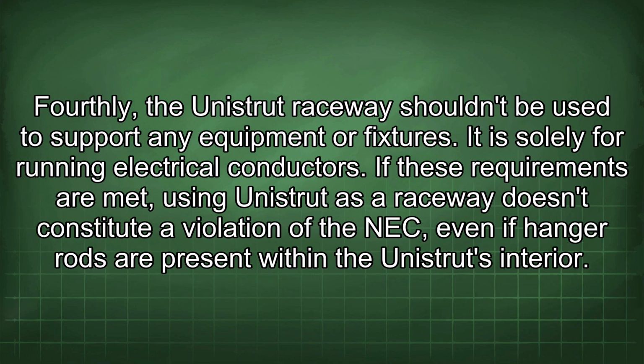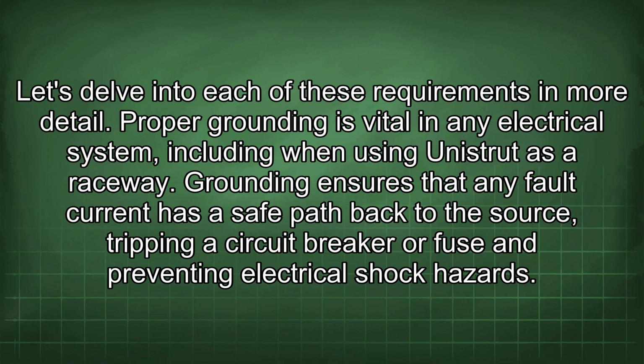Fourthly, the Unistrut raceway shouldn't be used to support any equipment or fixtures. It is solely for running electrical conductors. If these requirements are met, using Unistrut as a raceway doesn't constitute a violation of the NEC, even if hanger rods are present within the Unistrut's interior. Let's delve into each of these requirements in more detail.